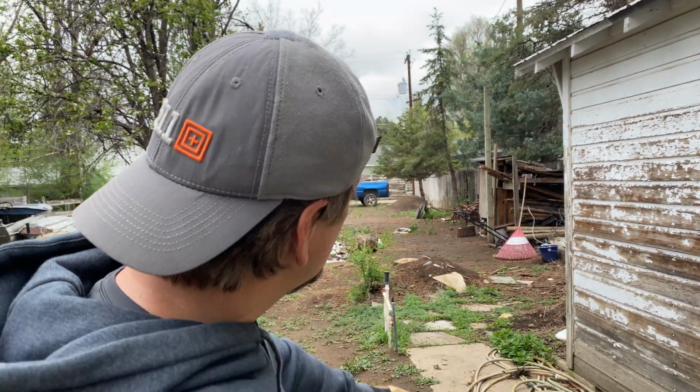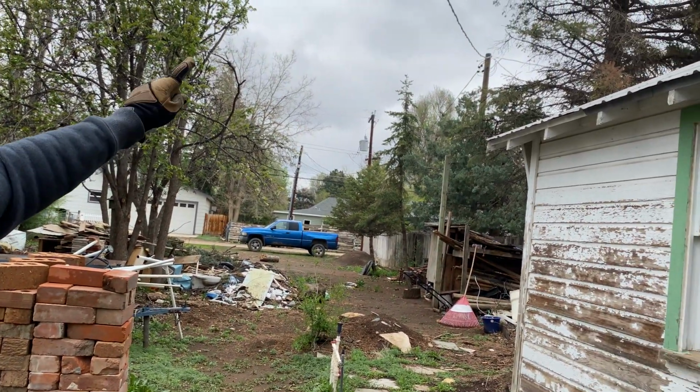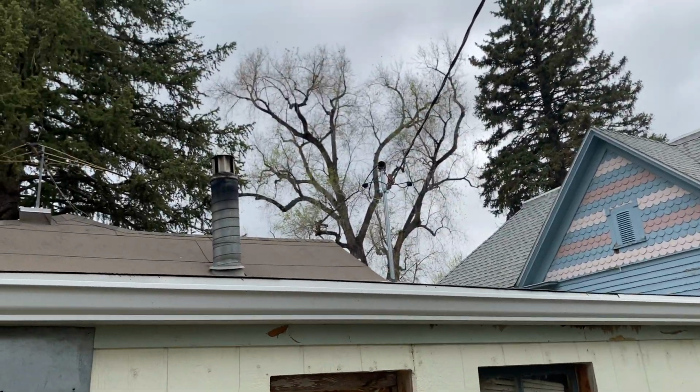And so for some of these situations, it's going to be really tricky because see, it went from that transformer to this pole, from this pole to this house. And so I actually lost a job last week on that because I did not know that and they didn't send me an email. 6 years ago, you were allowed to stay 200 amps overhead. 5 years ago, 150. Now, for the last 4 years, it's been 100 amp, nothing more, and you can stay overhead. They don't want it.